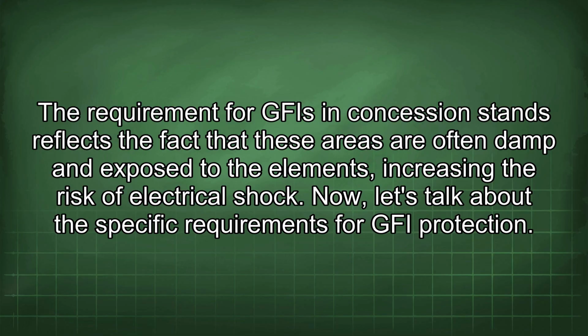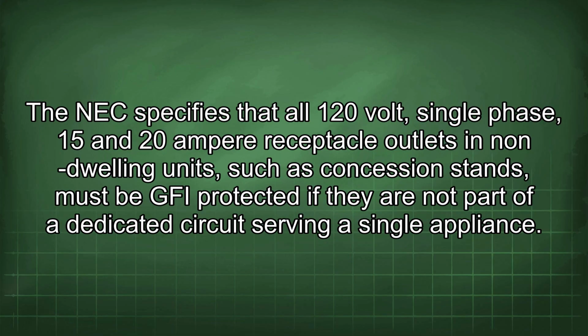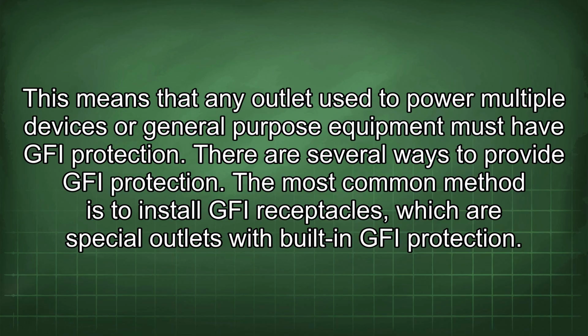Now let's talk about the specific requirements for GFI protection. The NEC specifies that all 120-volt, single-phase, 15 and 20 ampere receptacle outlets in non-dwelling units, such as concession stands, must be GFI protected if they are not part of a dedicated circuit serving a single appliance. This means that any outlet used to power multiple devices or general-purpose equipment must have GFI protection.